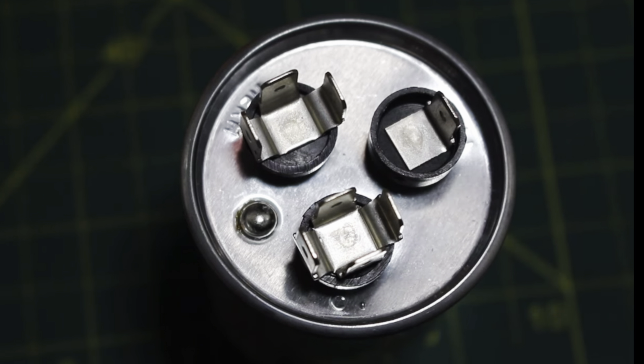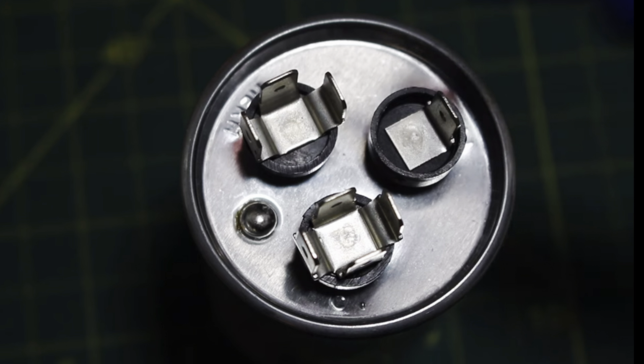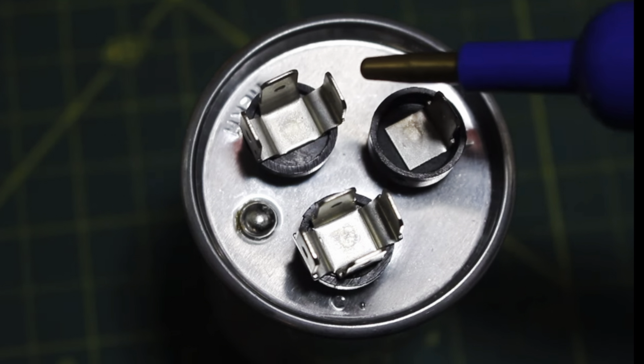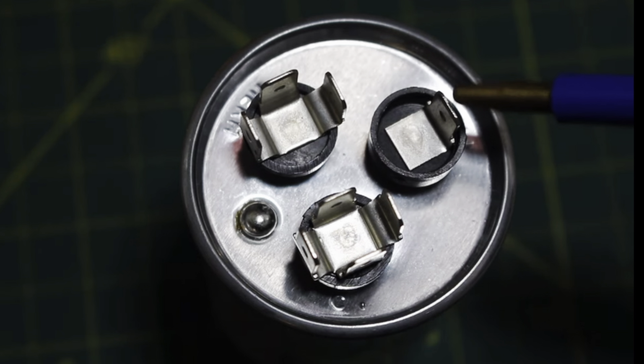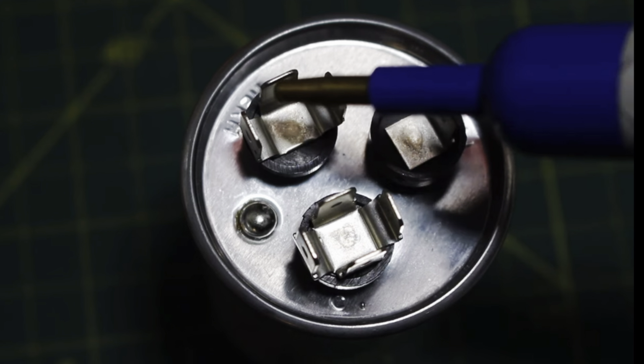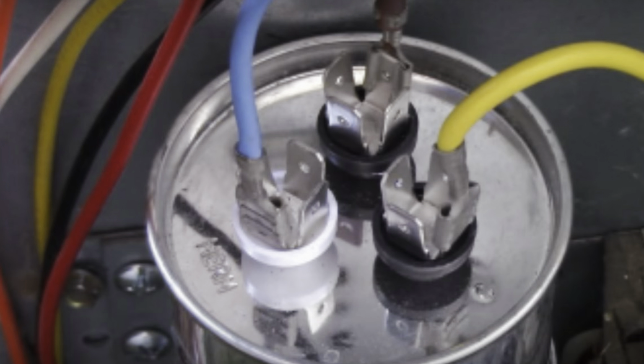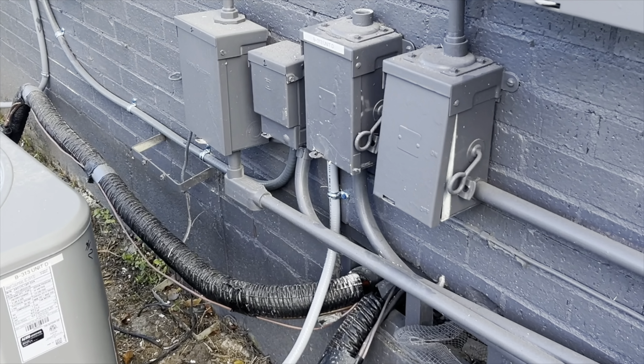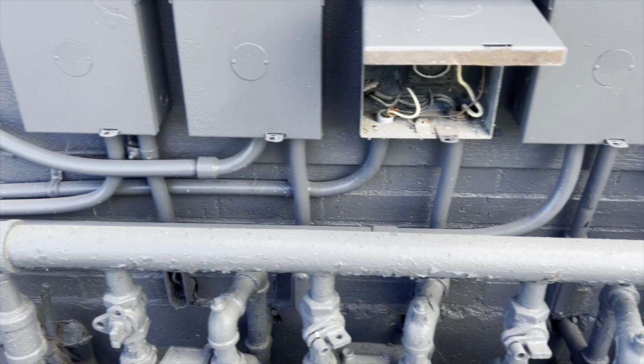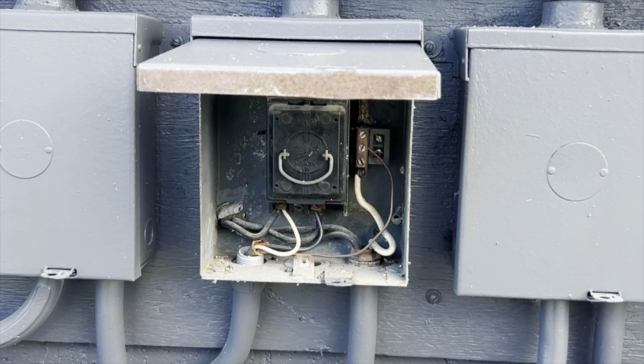The capacitor leads can be identified by the letters on the capacitor or by the number of prongs. The common usually has 4 prongs. The Herm or compressor side would have 3 prongs, while the fan side would have 1 or 2 prongs. Different brands use different identifiers, so always be sure to test it before you install it. If the outside unit is still not responding and the disconnect is on, the issue could be within a fuse just under the main meter.